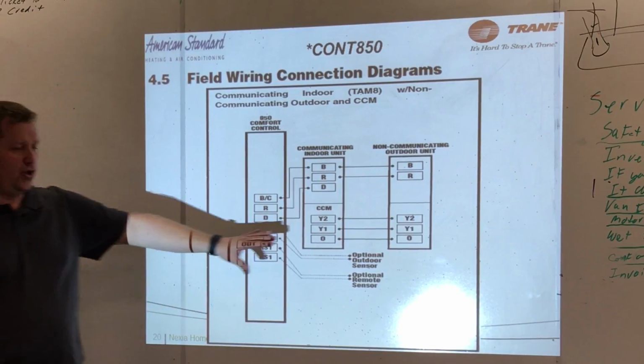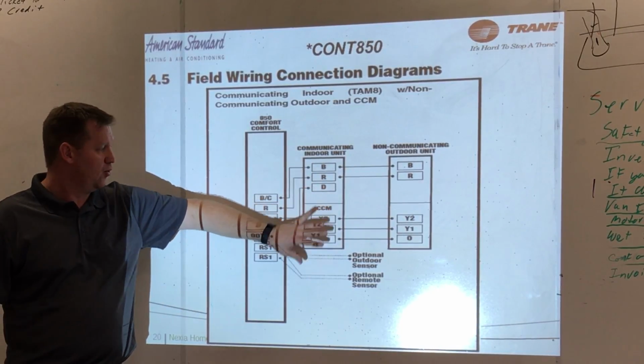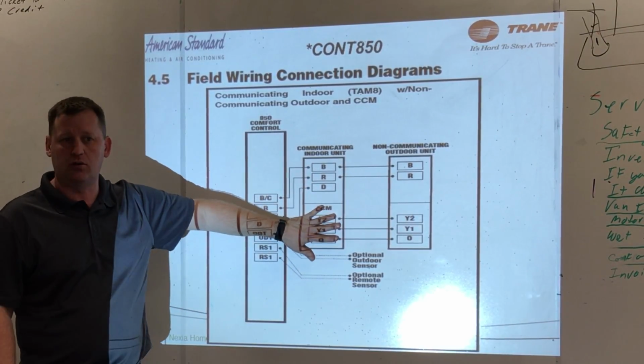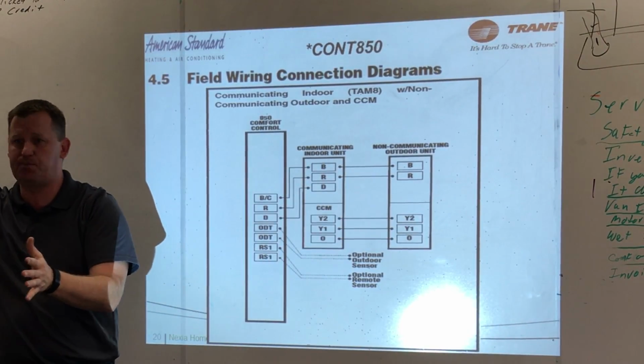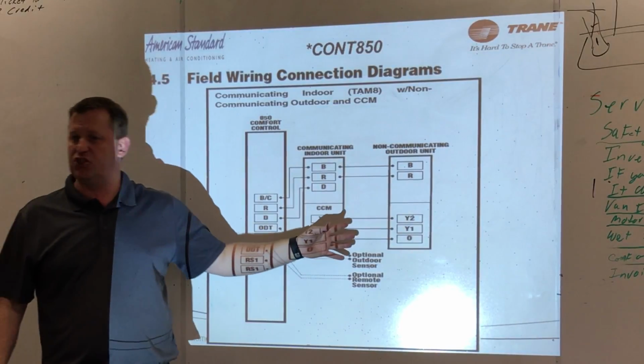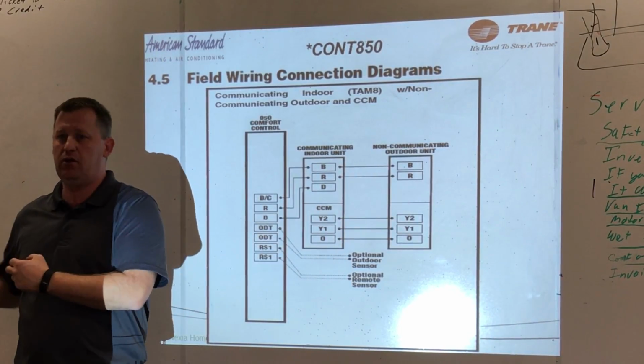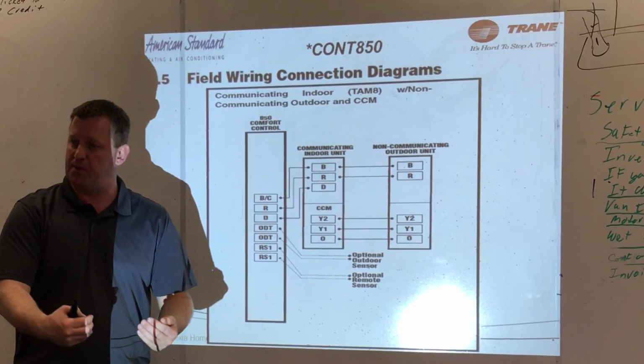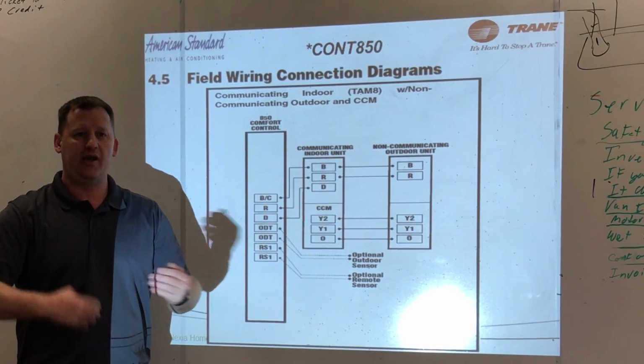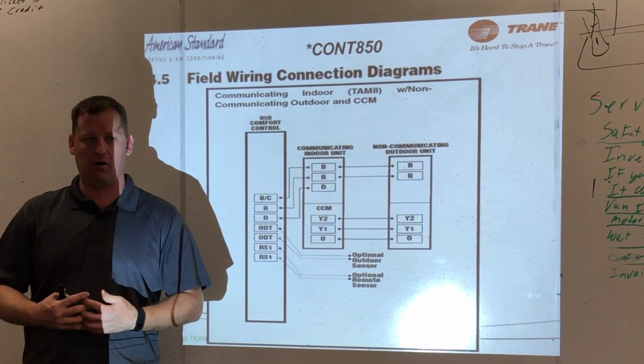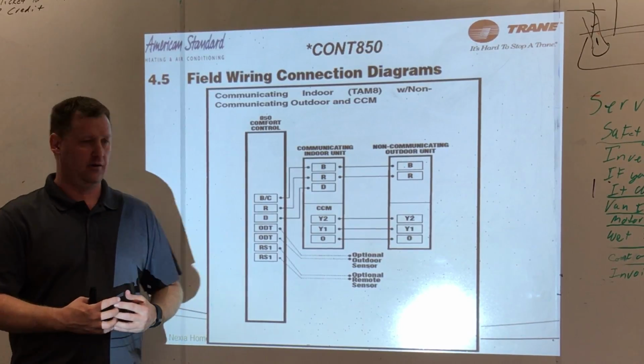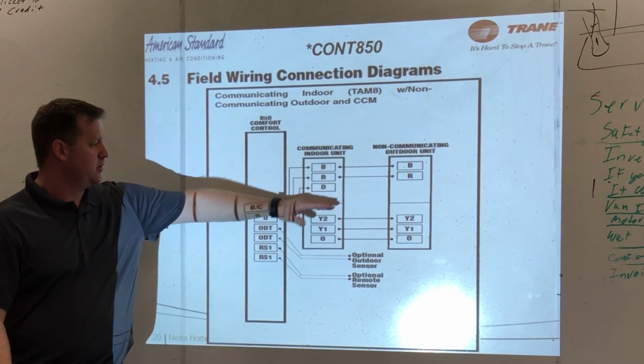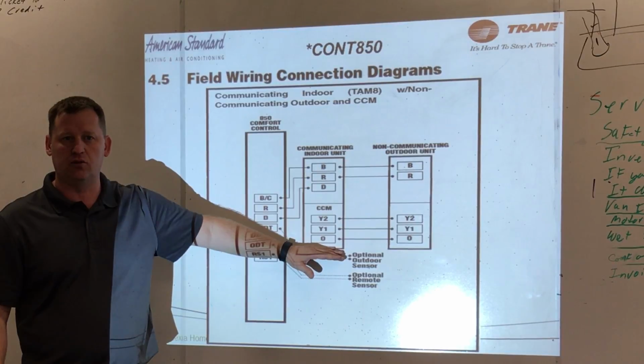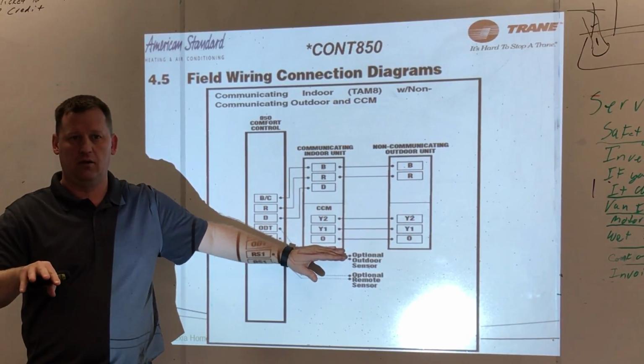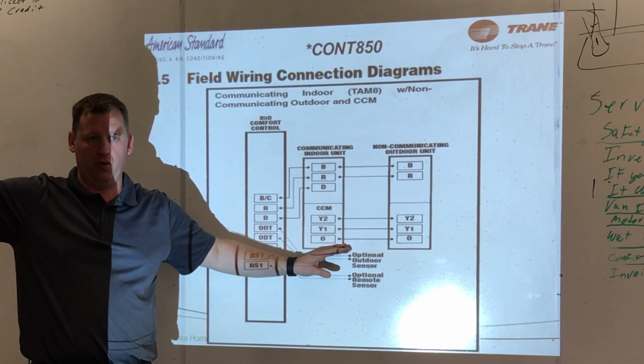All right. When you guys have added the compressor control module, because they did the air handler this year, and now next year they're doing the variable speed outdoor unit, you've had an issue where you come in, pull off the old outdoor unit, put on the variable speed outdoor unit, and now you've got multiple outdoor unit error codes, right? We battled this one a while back. As soon as you pulled off the compressor control module, reset the stat, second outdoor unit went away, right?